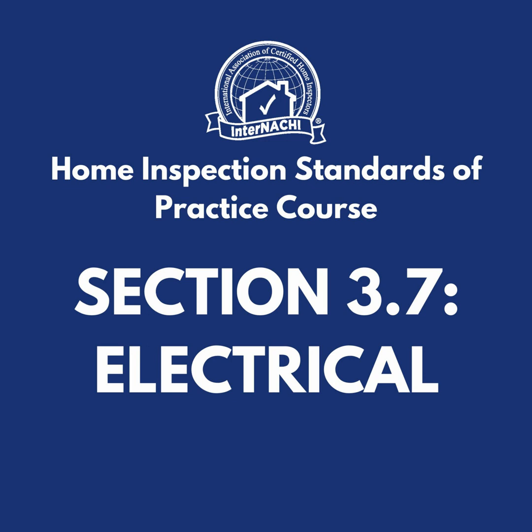Grounding and bonding. Generally speaking, the difference between grounding and bonding is grounding is a direct connection to the earth to aid in removing damaging, transient overvoltages due to lightning. The purpose of bonding is to ensure the electrical continuity of the fault current path to provide the capacity and ability to conduct safely any fault current likely to be imposed and to aid in the operation of the overcurrent protection device. Properly bonding all metal parts within an electrical system helps ensure a low impedance fault current path. The issue of grounding and bonding confuses many inspectors. Due to its complexity, we highly recommend taking the free online How to Perform Residential Electrical Inspections course.